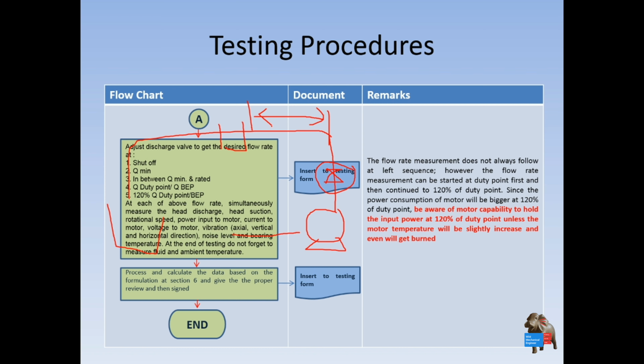After you divide into at least 5 points, let's say you want to test the pump performance with a design flow capacity of 100 cubic meters per hour. You have to test at 0, and then at the design point of 100 cubic meters per hour, then 120% of the design point, and then points in between the minimum and the design point. So you will have at least 5.